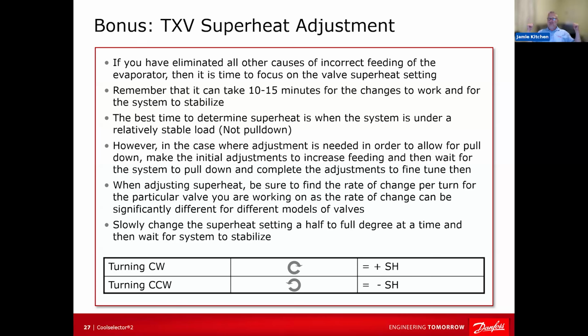So it's like if you're out in the woods and you go into a log cabin, you put the wood stove on, the air heats up. If you turn that fireplace off, the temperature is going to plummet because the mass of the building is way more than the air. So the superheat's going to start moving. You don't want to adjust it when the superheat is moving because it's a moving target. Now, if you're not pulling down and the superheat stays high, then you can maybe adjust it in steps to get it down.